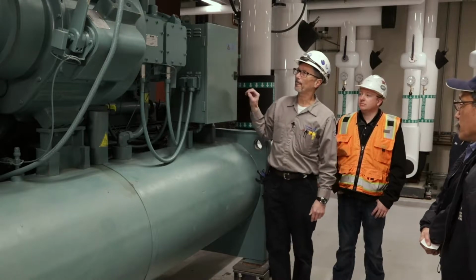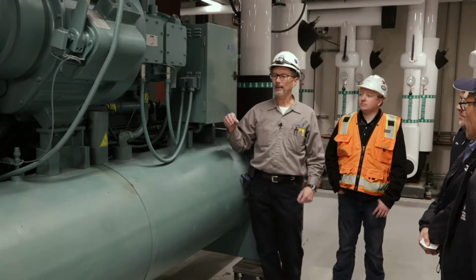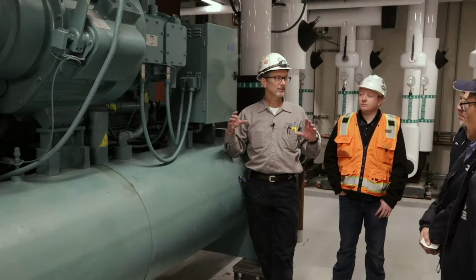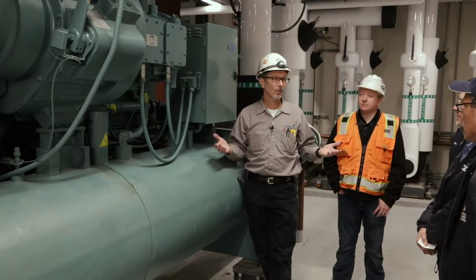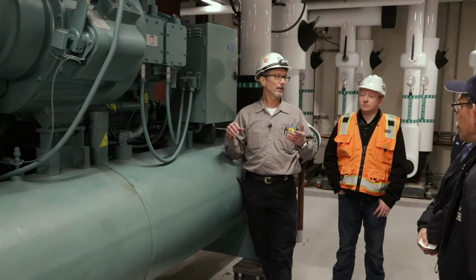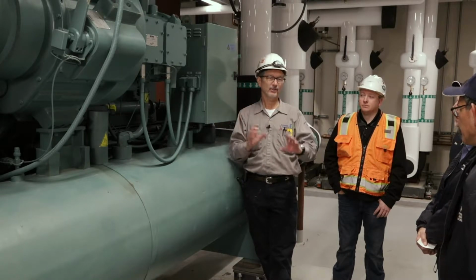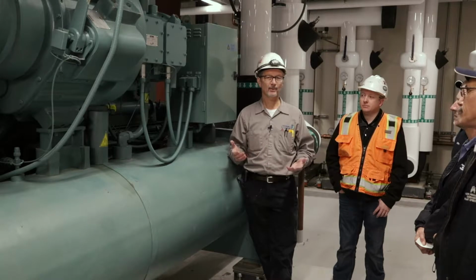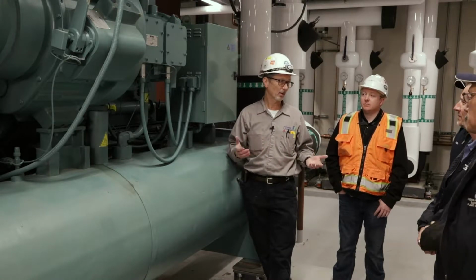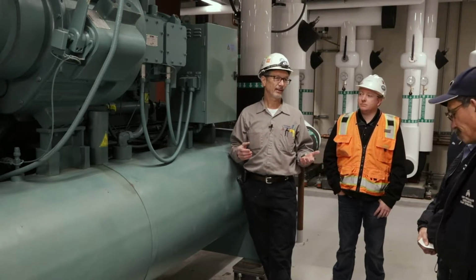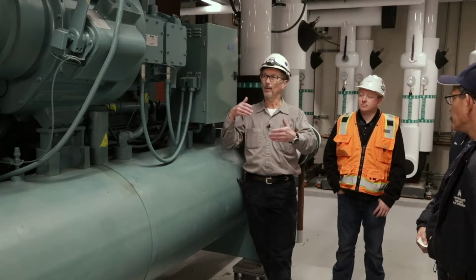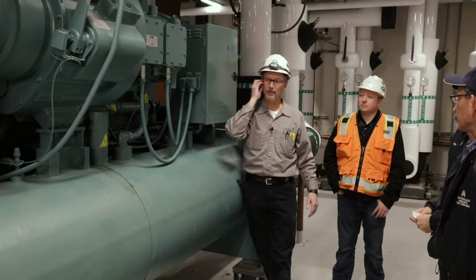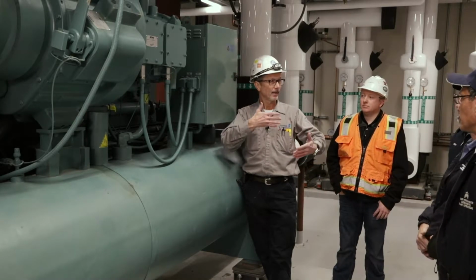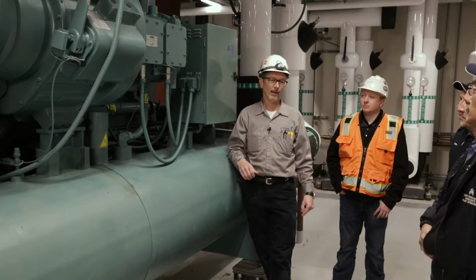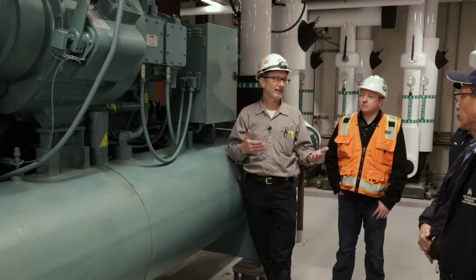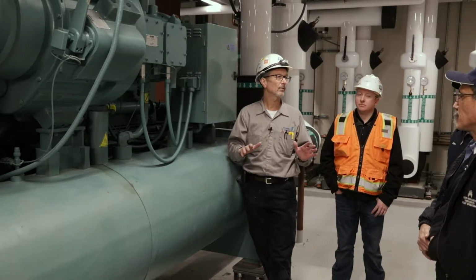So this thing has touchdown bearings so that if something happens, if you lost power and the motor was running, it wouldn't ruin itself by touching down where there wasn't a bearing. Those bearings aren't designed to have any runtime on them, but it prevents any damage in case it touches. Or if there's a mechanical issue or something happens with the impeller and it gets out of balance somehow, those prevent any damage, and it senses all that and shuts everything down.